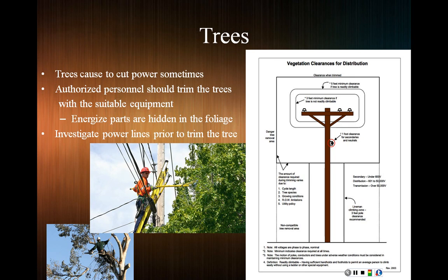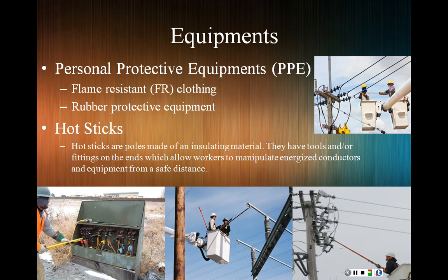If you can climb the trees, the clearance distance for trimming should be 5 feet, but if you cannot climb, the clearance distance should be 3 feet. This clearance distance is based on cycle length, tree species and growing conditions, right of way limitations, and utility policies. We should use personal protective equipment. As you can see in the picture, helmets and gloves should be insulated against electricity, along with flame resistant clothing.